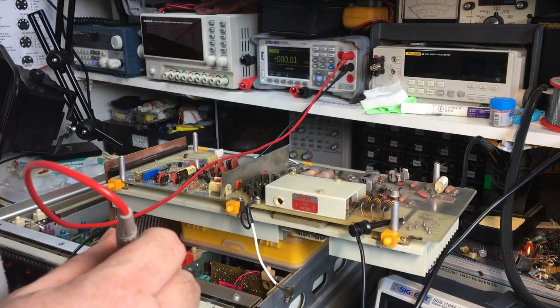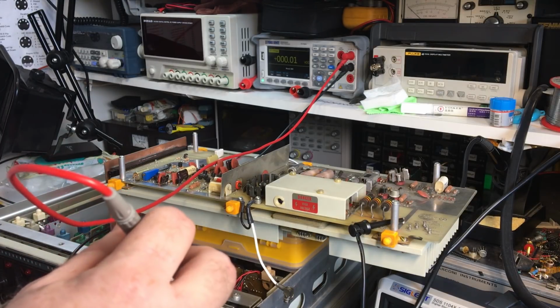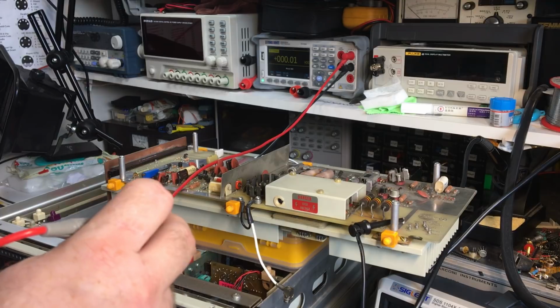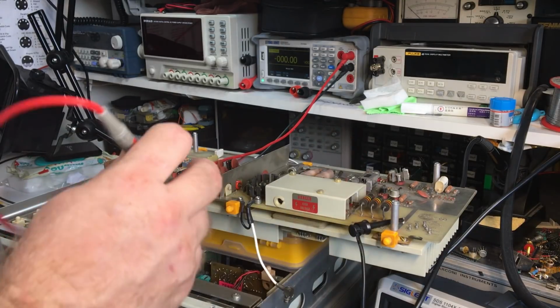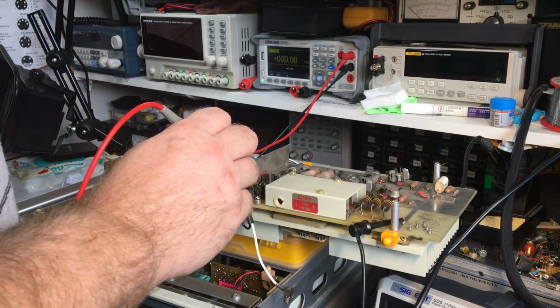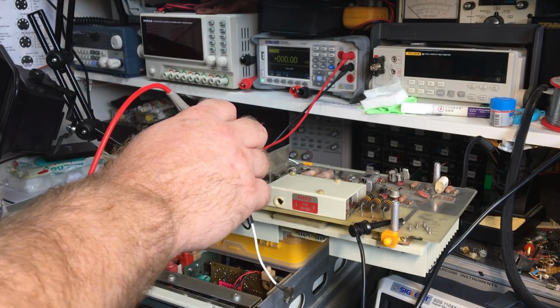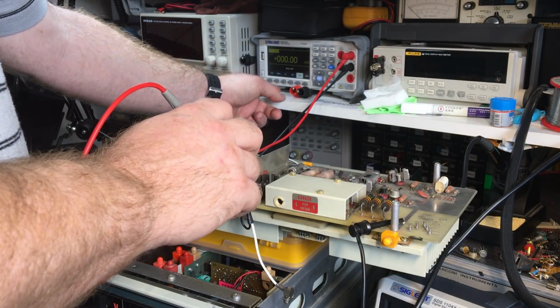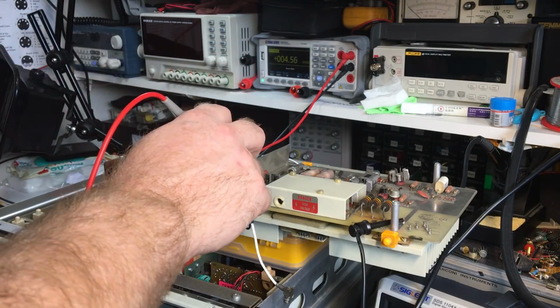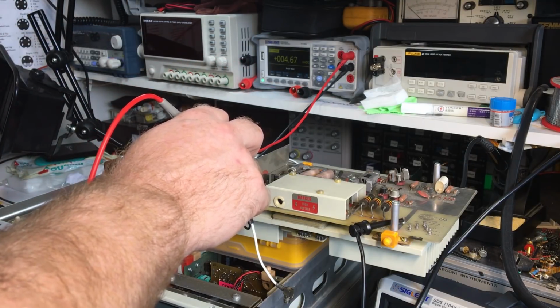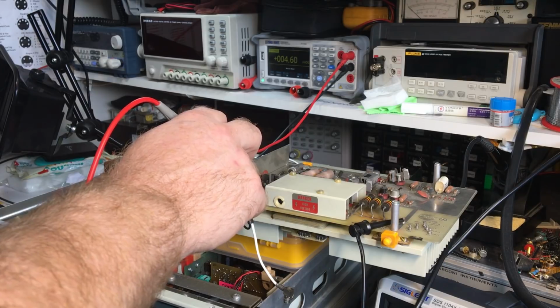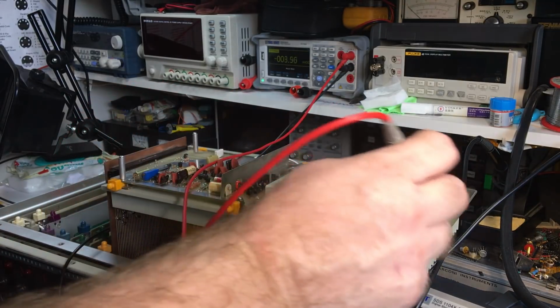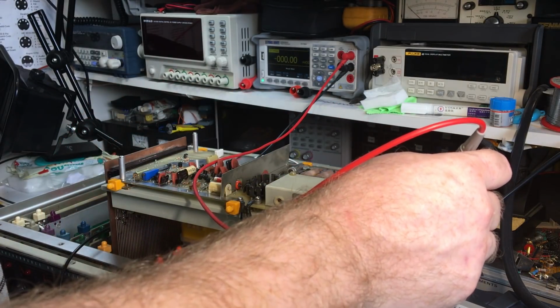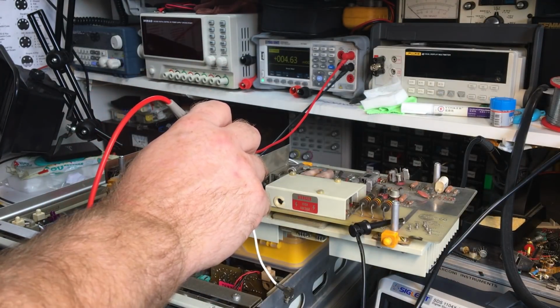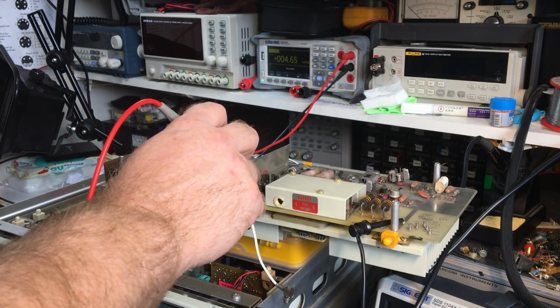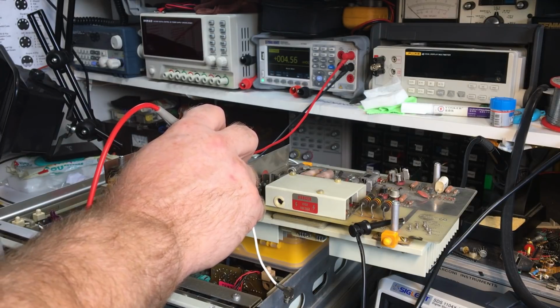Okay, so the next step is step 41, jumps to, and I've got to check the DC offset between the output and TP6. So I'm still on TP6 here, so the output is right here. 0 volts. So it should be a very low reading, 0 volts plus or minus microvolts. I'm getting millivolts here. If I just make sure the zeroing is okay. Yes, it is. So there is a slight offset there. Why there's an offset there, I don't know.